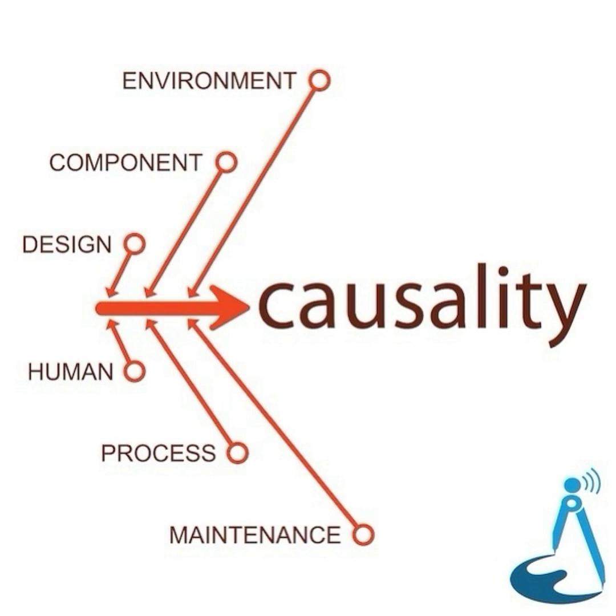Beyond the technical cause and effect that led to this incident, PowerLink could have opened the Unit C4 circuit breaker at Calvale substation at any time, but wanted clearance from CS Energy to do so, which was never given because the operators had been evacuated at different times, or when they were on site, they weren't sure it was safe to do so for fear the turbine would overspeed due to a lack of information, due to a lack of SCADA, due to a lack of manual indication they could safely observe.